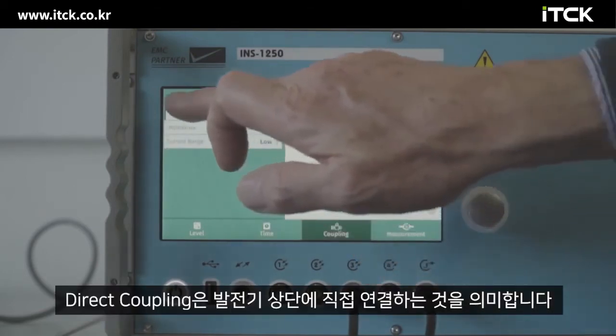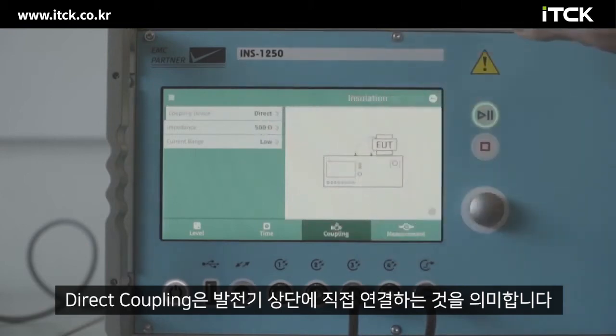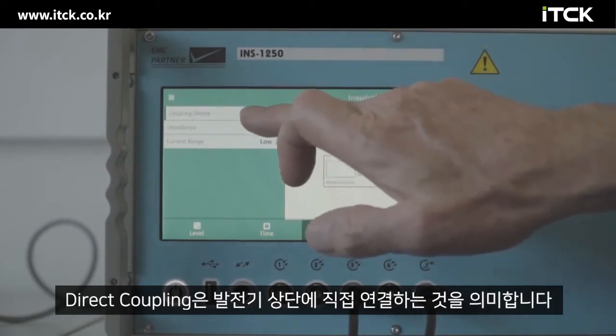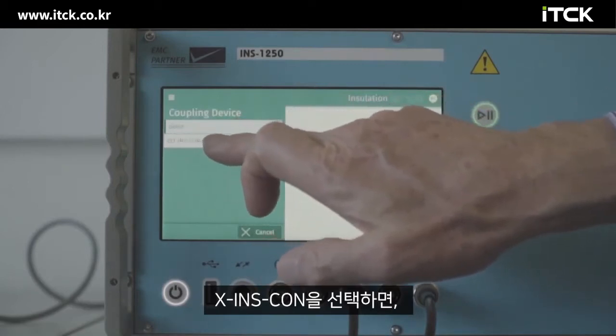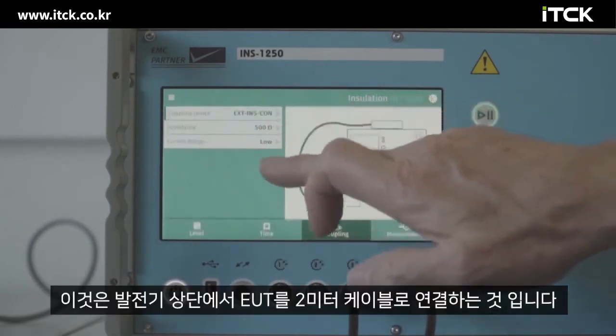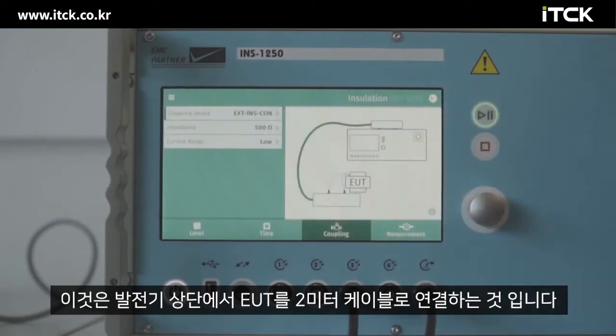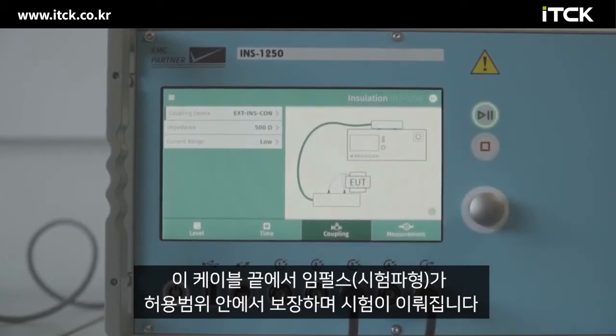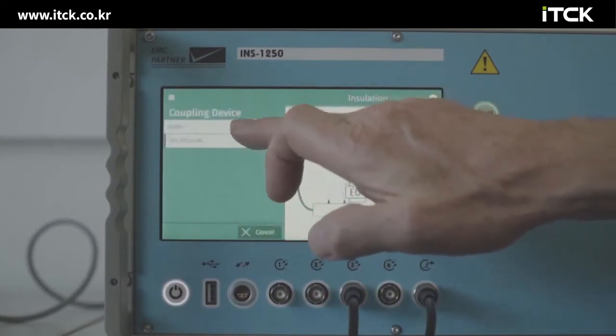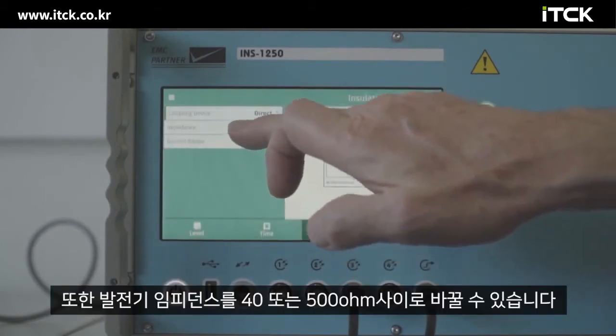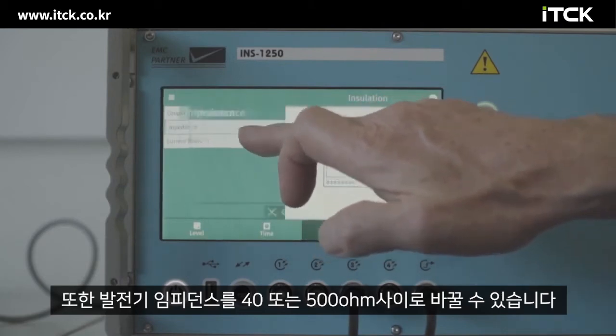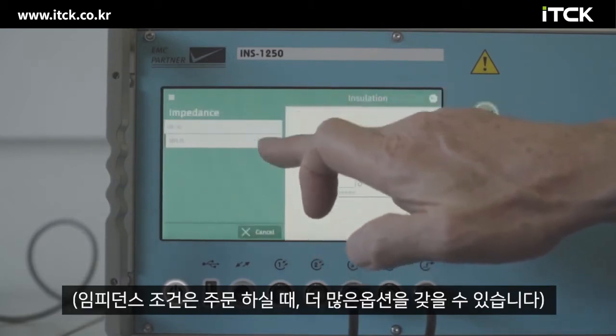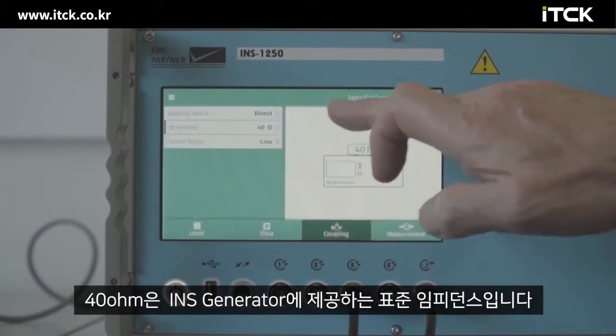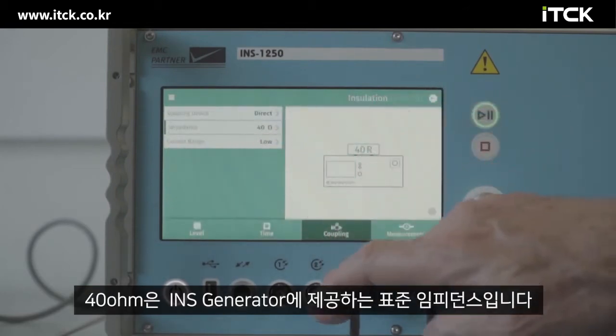Coupling. Direct coupling means connection directly on the top of the generator. If we select the EXT-INS CON, this is a 2-meter cable which connects from the top of the generator to the test object, and at the end of this cable we guarantee that the impulse is within tolerance. We can also change the generator impedance between 40 and 500 ohm. 40 is the standard that we provide with the generator.